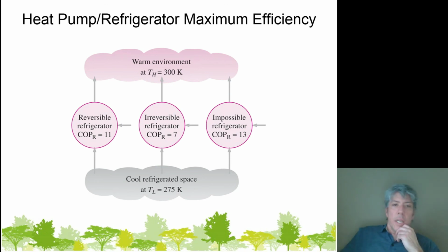Now, with a heat pump, you may know that heat pumps are not typically all that popular. The reason is because engineers understand this, and so if you make a heat pump, you really don't want to take the air that you're blowing throughout the house up to too high a temperature. I mean, if it's 30 degrees outside and you're trying to maintain a home at, say, 75 degrees in the wintertime or when it's cool outside, you don't want to take the air up to 200 degrees or something, because the maximum theoretical efficiency will be capped so much by that high temperature. Rather, you'd like to take the air to, say, 90 degrees or so, or maybe 80 degrees if the set point is 75.